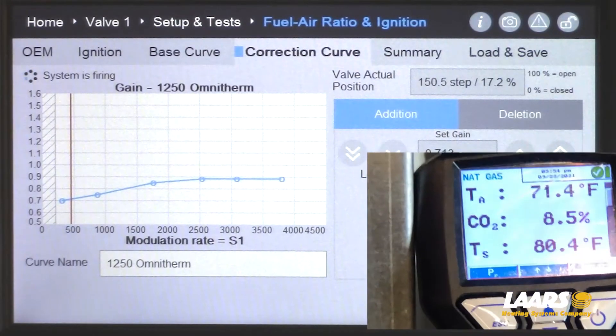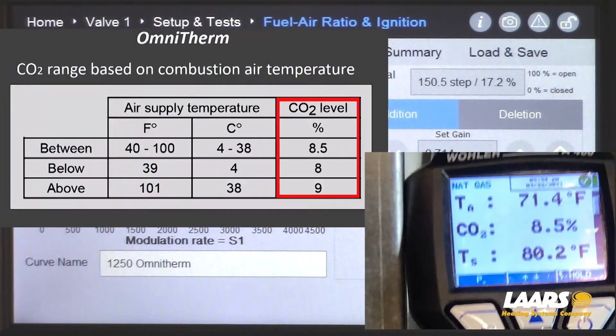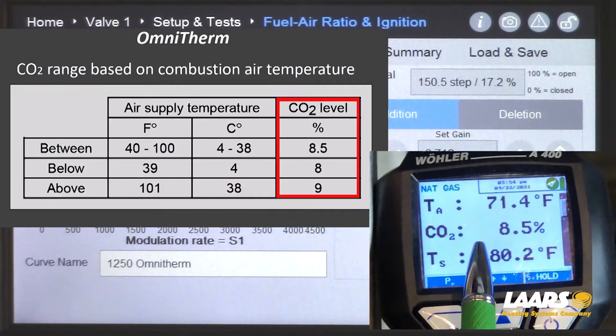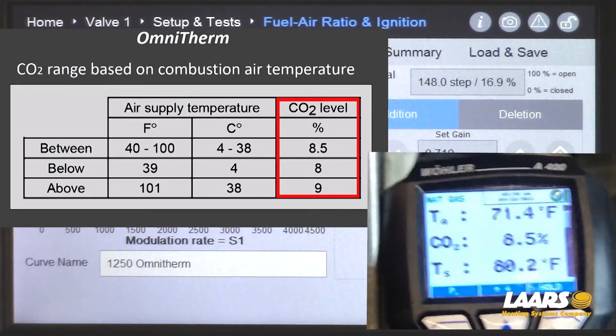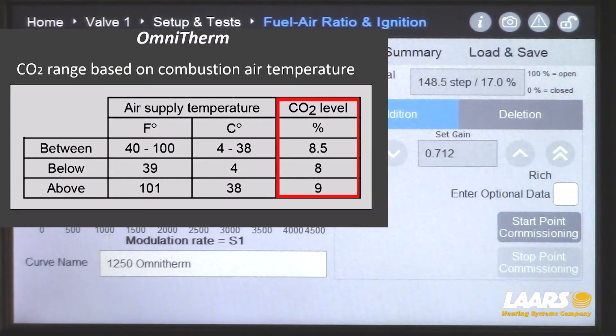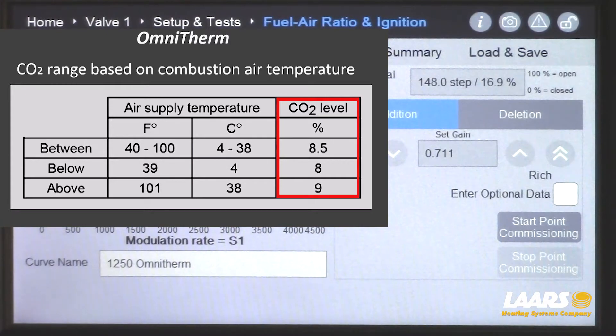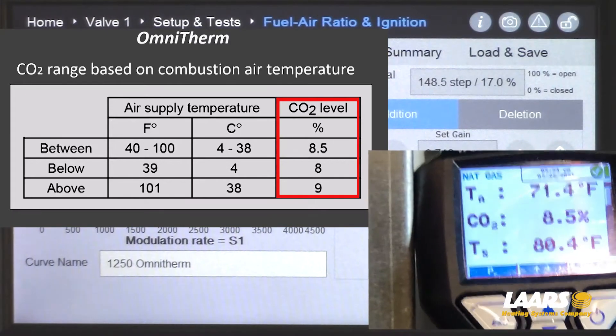Here is the combustion chart. Our air temperature in the training room is about 70 degrees, so we're looking for 8.5% CO2 — and we're there.